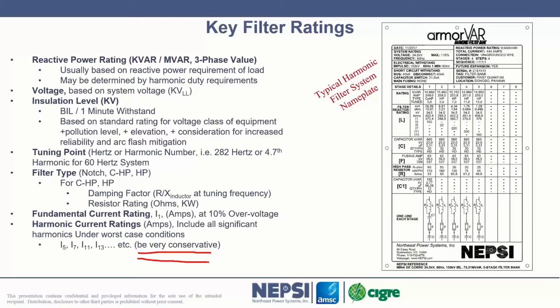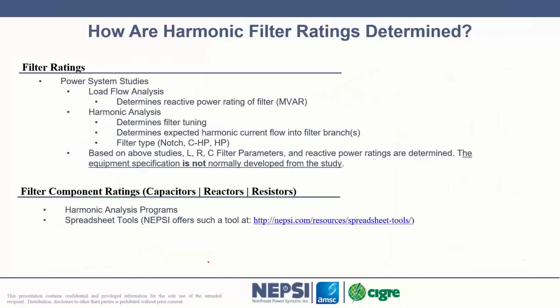It's a true fact. Oftentimes we see consulting firms develop a specification based upon the results of a harmonic study, and they will specify those exact harmonic currents that the harmonic study put out. That's just simply not a good practice to follow. We recommend a significant amount of conservatism be put into that filter design. Because why? Because systems change. And so we'll talk about that a little bit.